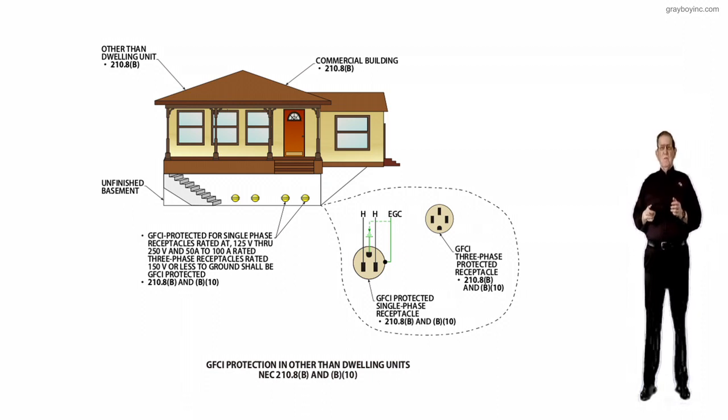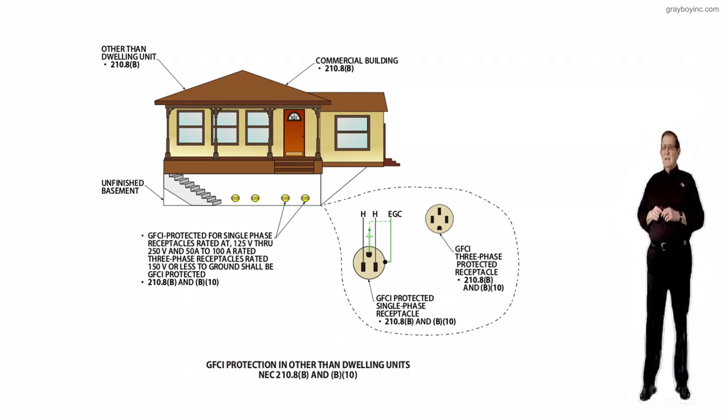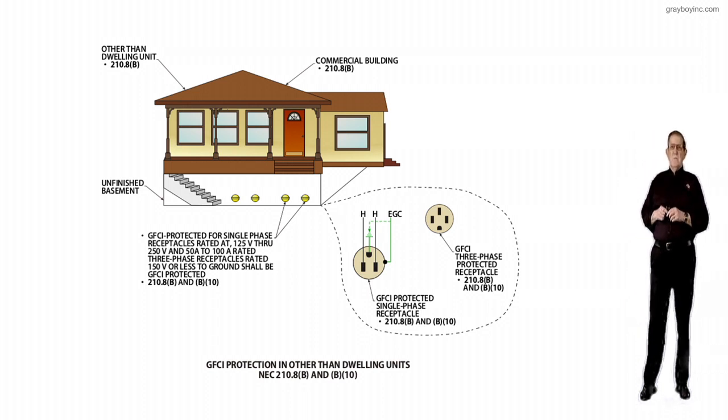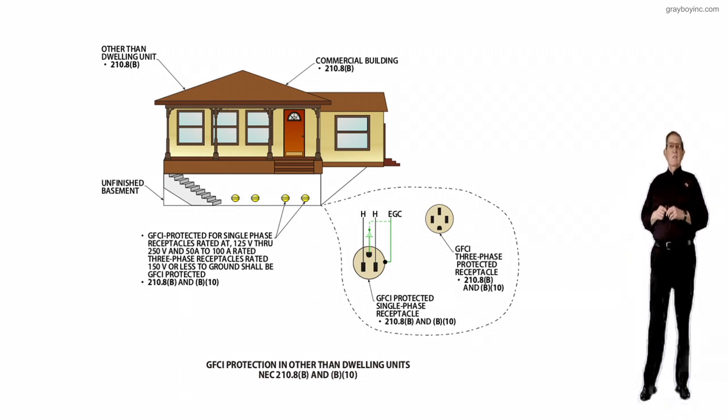The purpose of change is a revision that has been made to clarify that ground fault protection for personnel should be provided on all 120-volt through 250-volt receptacles installed in unfinished basements, as well as three-phase receptacles rated at 150 volts or less to ground at 100 amps or less.